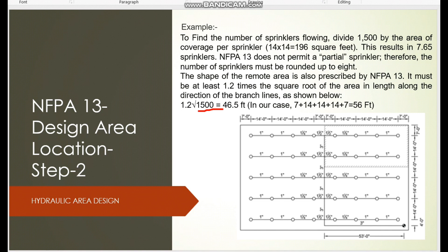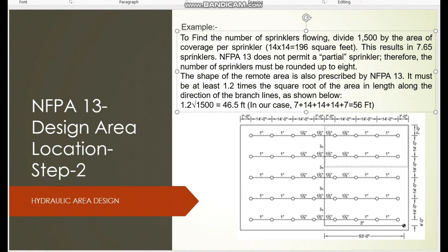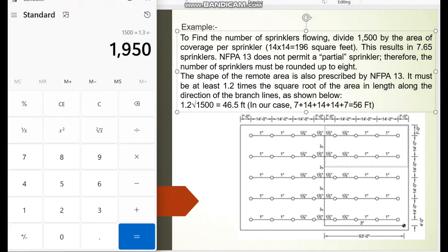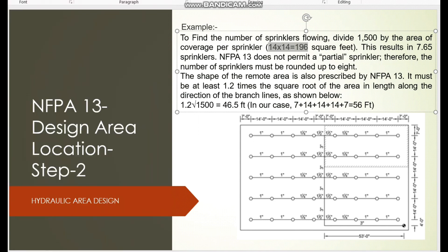Coming back to our example: the hydraulic area is 1500 square feet. If we assume a dry system, we must increase the hydraulic area by 30 percent: 1500 × 1.3 = 1950 square feet. Since one sprinkler protects 196 square feet, we divide 1950 by 196, giving approximately 9.9 — so we need to consider 10 sprinklers.